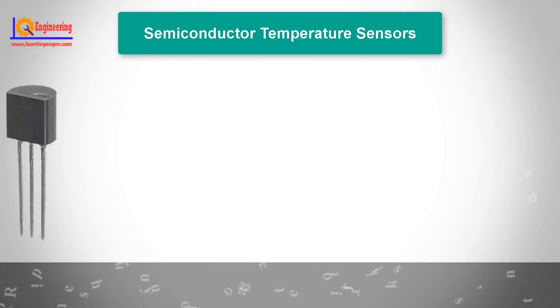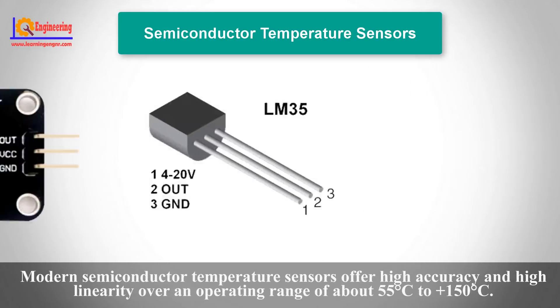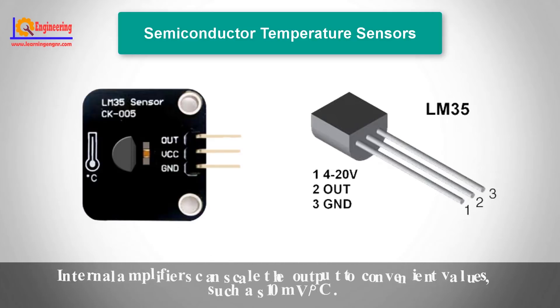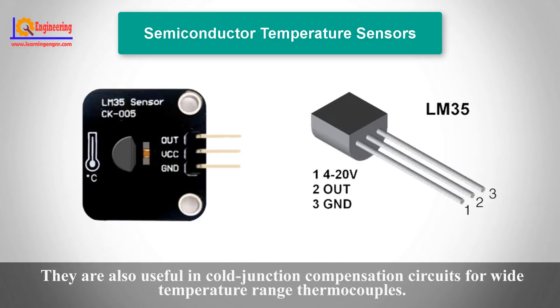Semiconductor sensors are classified into different types including voltage output, current output, digital output, resistance output, silicon, and diode temperature sensors. Modern semiconductor temperature sensors offer high accuracy and high linearity over an operating range of about -55°C to 150°C. Internal amplifiers can scale the output to convenient values, such as 10 mV per degree centigrade. They are also useful in cold junction compensation circuits for wide temperature range thermocouples.